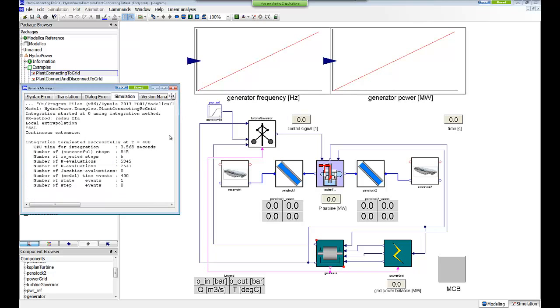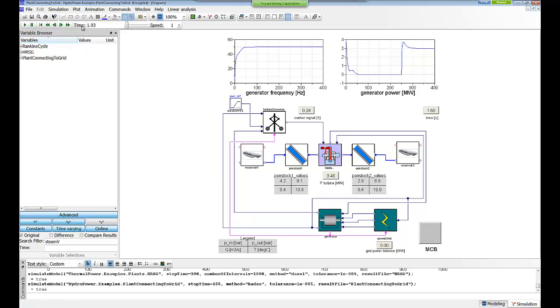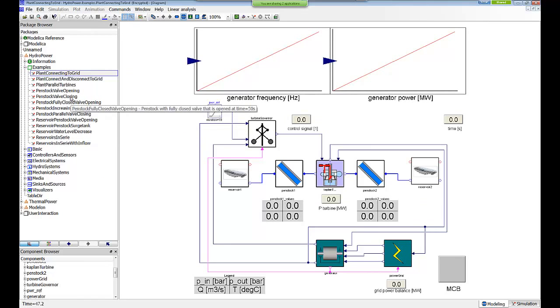So it should go really quick here. So you see that I simulated 400 seconds and it only took under four seconds to do it. So I go to the simulation button, I press here the diagram so we can have some visualization. So you can see what's happening at the bottom here. You see pressure in and out of the penstock, the flow in cubic meter per second, and temperature, etc. And at the top here you see generator frequency and the generated power. So we specified in the generator that we should try to connect at time equals to 250 seconds. This is when we connect to the grid and this is when we start to produce power from the hydropower plant here.